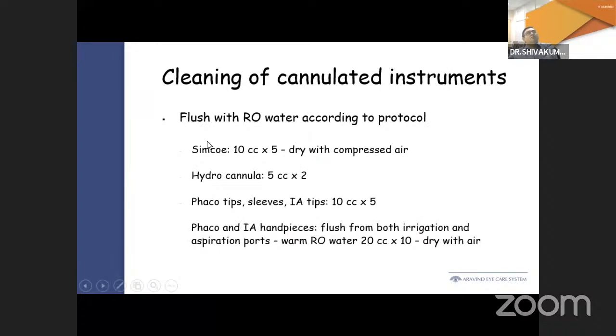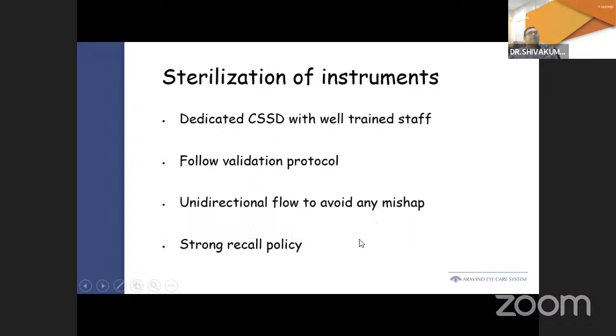As far as cannulated instruments are concerned, the Simcoe is to be flushed with 10 cc 5 times, hydrocannula 5 cc twice. The phaco tips and sleeves and IA tips 10 cc 5 times. Phaco and IA handpieces should be flushed from both the irrigation as well as the aspiration ports with warm RO water 20 cc 10 times, and an equal amount with air so that they can dry.